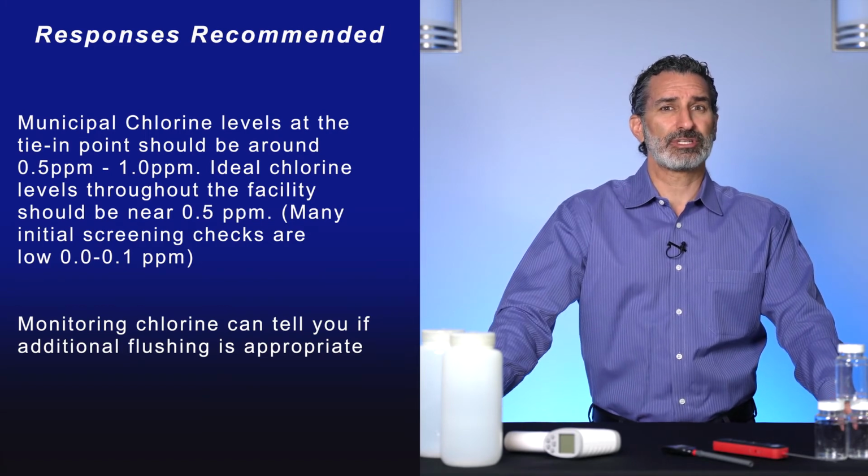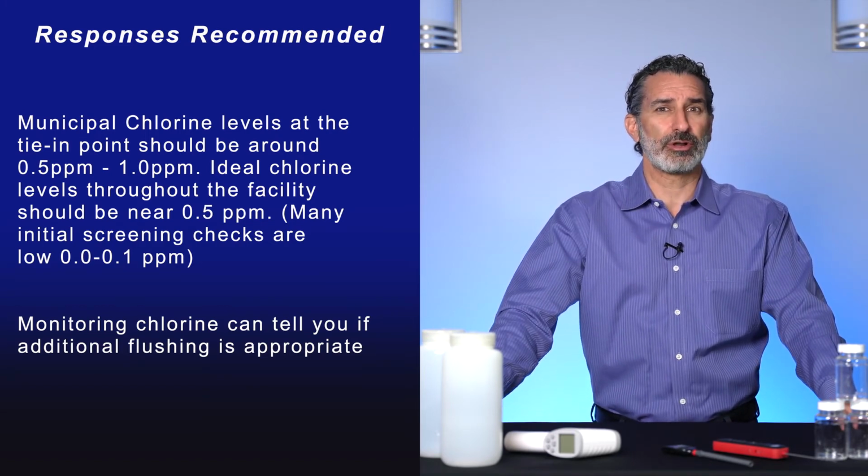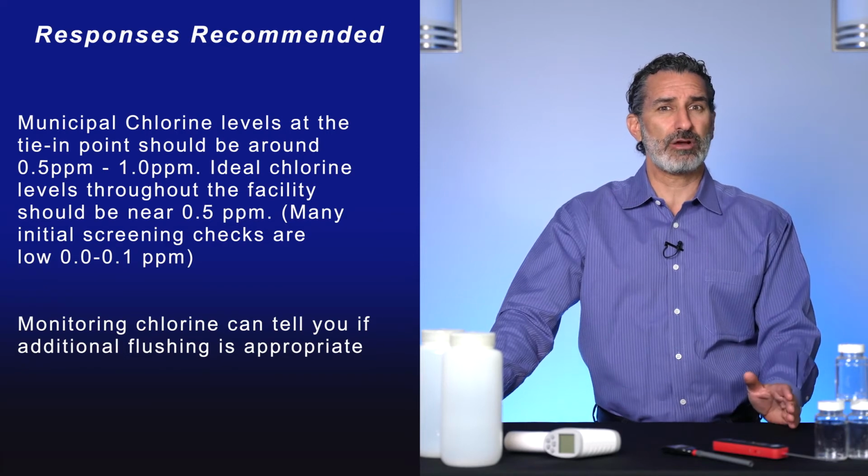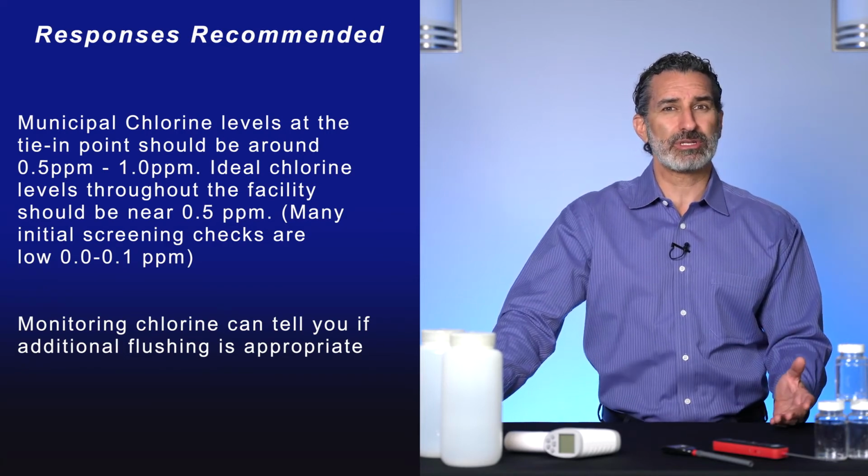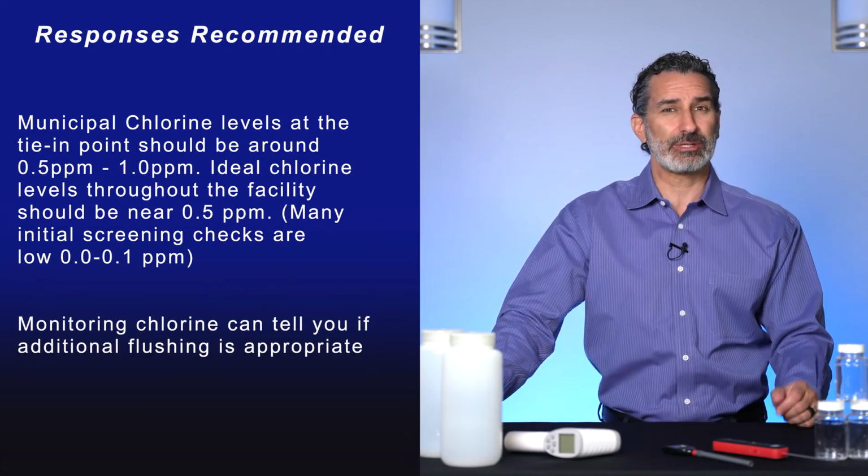That's why it's important to continuously flush your water system. Just like your pool at home, you don't add chlorine once and forget about it. You must continually add chlorine to your pool, which is a little bit difficult to do if you're trying to add chlorine into your water lines at your facility. So you must remove the water that is used or stagnant and bring in fresh or chlorinated water.